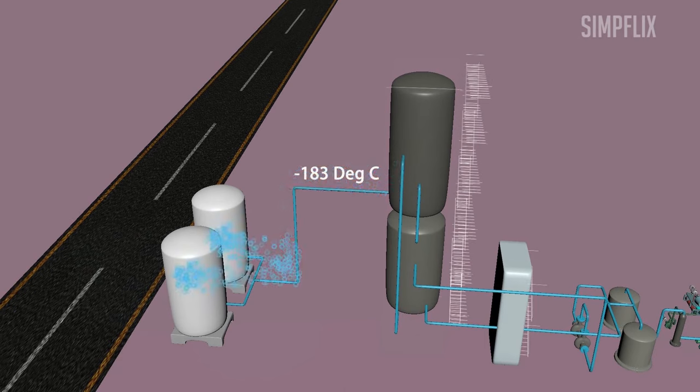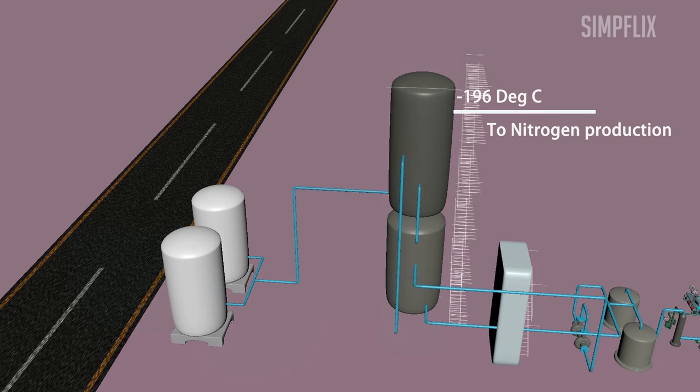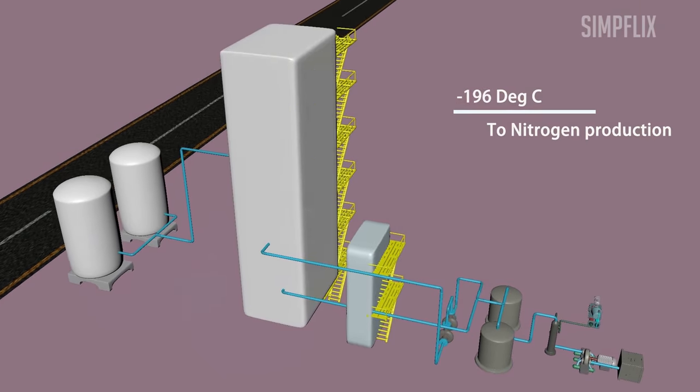Because of this temperature gradient, oxygen will be liquefied at minus 183 degrees Celsius area and collected. Argon will be liquefied at minus 186 degrees Celsius area and collected. Nitrogen will be liquefied at the top column where temperature is at minus 196 degrees Celsius and collected.